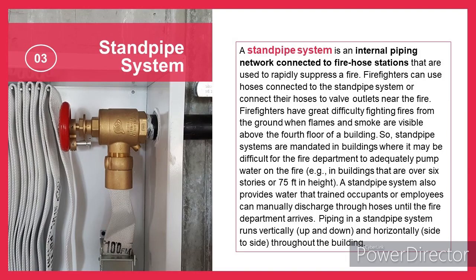A standpipe system is an internal piping network connected to fire hose stations that are used to rapidly suppress a fire. Firefighters can use hoses connected to the standpipe system or connect their hoses to valve outlets near the fire. Firefighters have great difficulty fighting fires from the ground when flames and smoke are visible above the fourth floor of a building. So, standpipe systems are mandated in buildings where it may be difficult for the fire department to adequately pump water on the fire, for example in buildings that are over 6 stories or 75 feet in height.